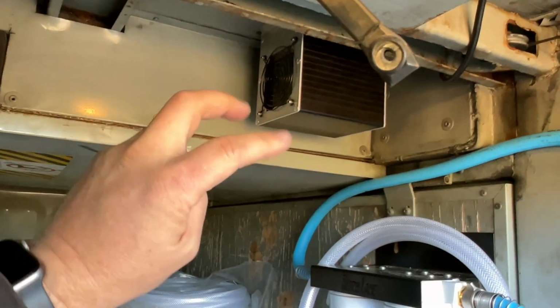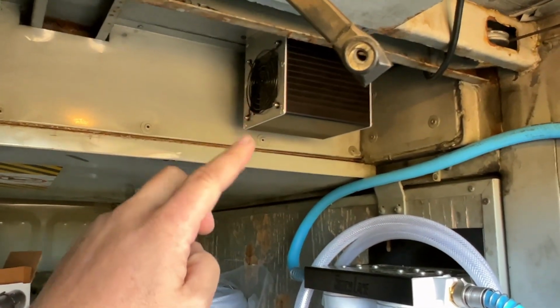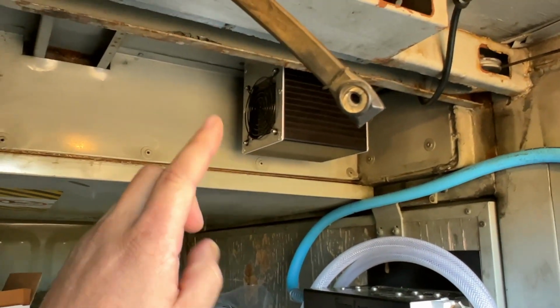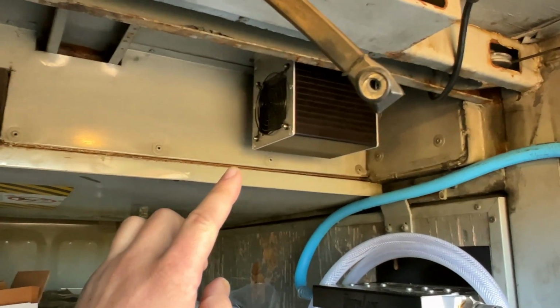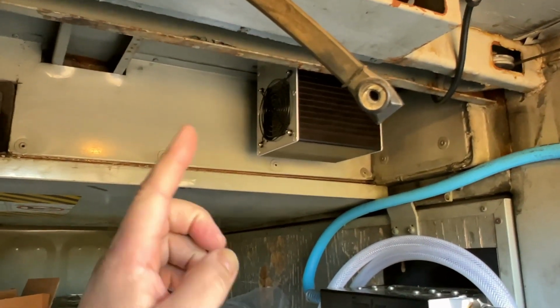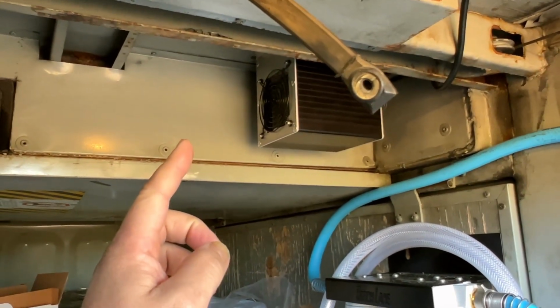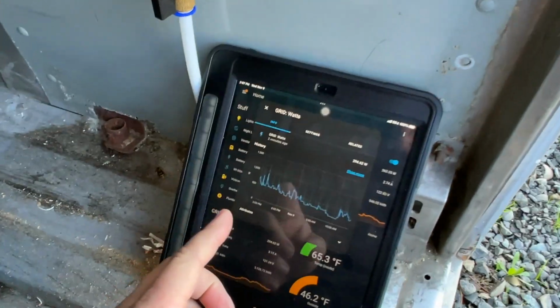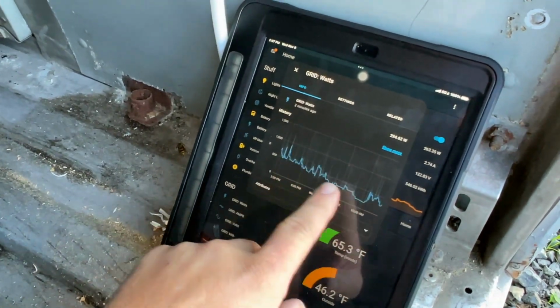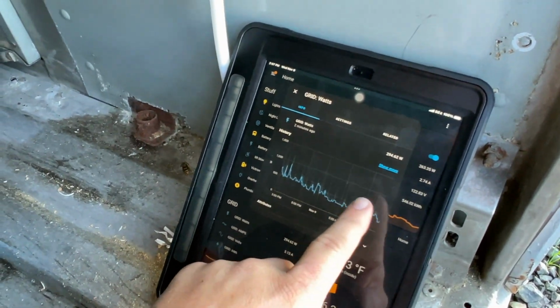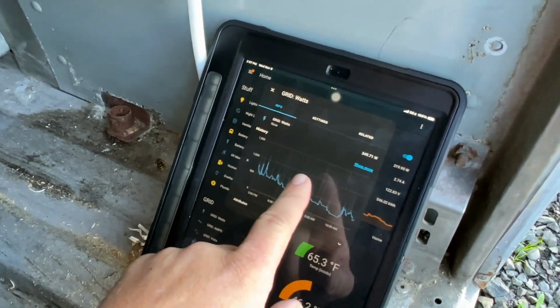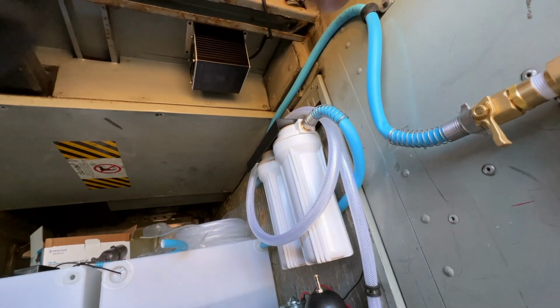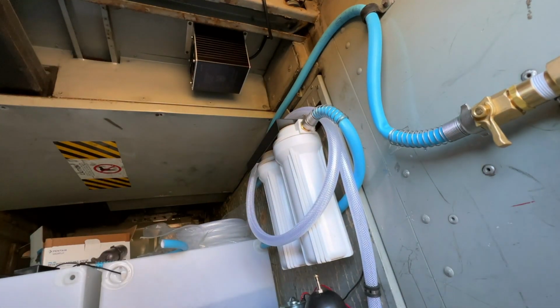While it's rated at 700 watts, the inrush current is going to be huge. It's rated for 6 amps under operation. The paperwork said the inrush was 12 amps, which is going to be maybe 1200 watts or something. But I need to be able to check and see what kind of spike that's going to show. So anyways, living in this bus with a fairly limited power feed, I have to be careful about how much power I pull and stuff.